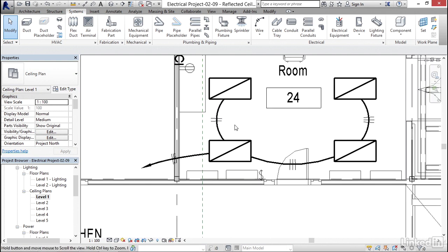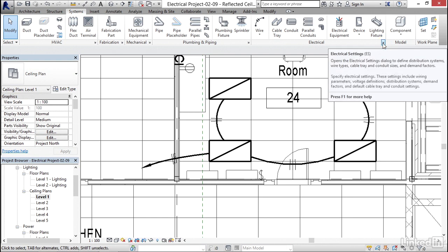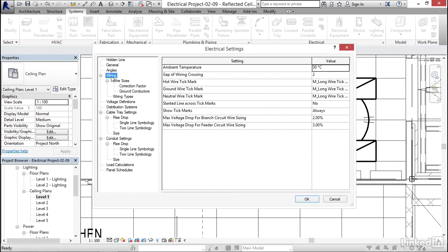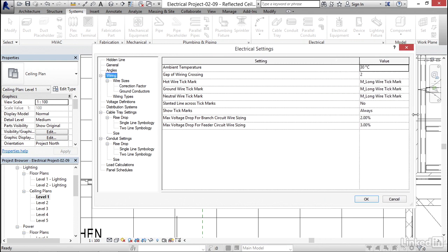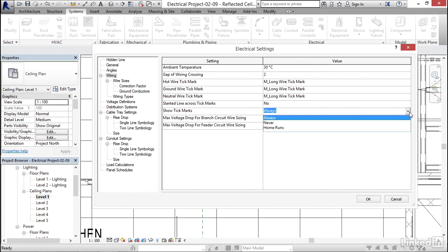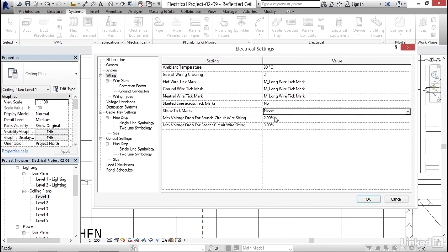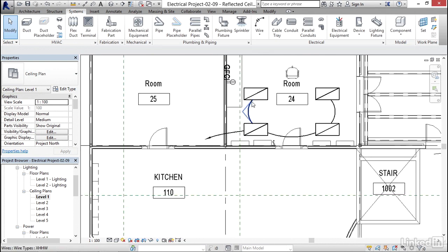So what I want to do is I want to go to electrical and I want to click the little electrical settings button right here. I want to click on wiring. And for show tick marks, we can do all of this stuff. So if I pan this over and I look at my settings, we can change how our tick marks look, or the way I do it is I never show tick marks. So instead of always, I'm going to click the drop down and I'm going to say never. I'm going to click OK. No more tick marks.